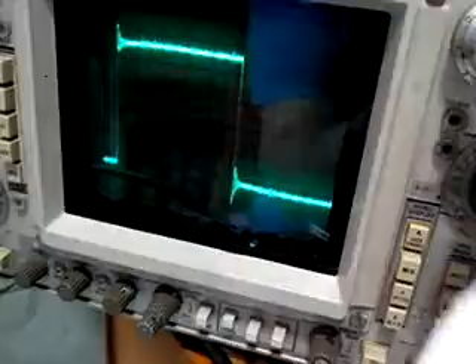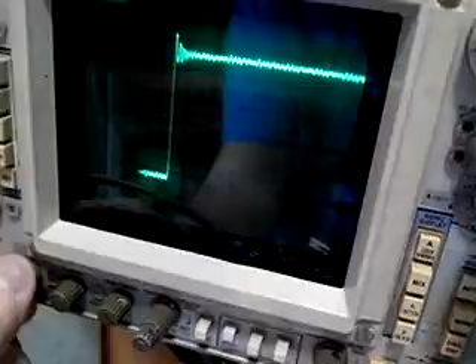And then the other issue is about the focus. Focus is pretty bad. Okay, I have adjusted all the way clockwise, and all the way counterclockwise, and as you see, it is asymmetrical. It gets the best focus, not in the middle, but somewhere near the beginning. Okay, I'm going to enlarge a little bit this 1 megahertz wave so that we can see better the traces in both directions, vertical and horizontal. I'm going to adjust the intensity to the best possible.